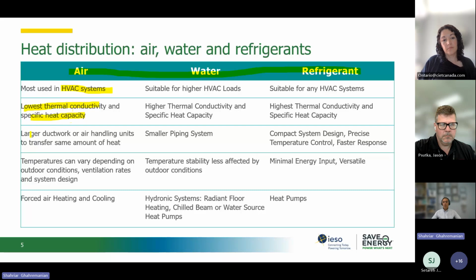And then, because of this, we need larger ductwork or air handling units to transfer the same amount of heat compared to water and refrigerant. Temperatures can also vary depending on the outdoor conditions. If we are talking about air source heat pumps, they become dependent on the outdoor weather. So again, extracting heat from outdoor air sometimes becomes a challenge, or also dumping heat from the inside to the outside.